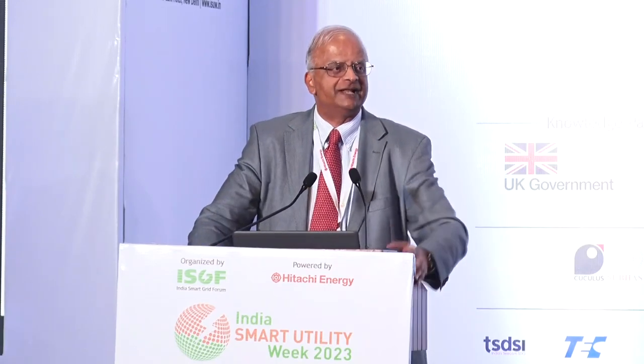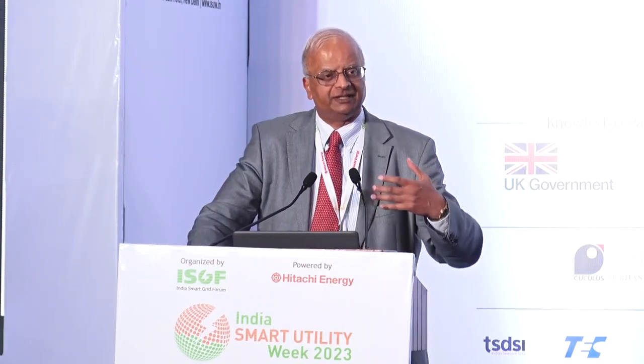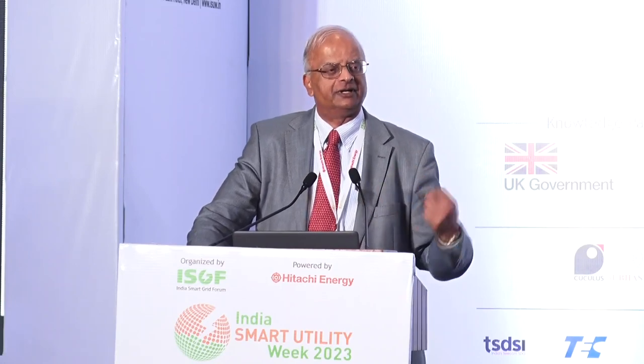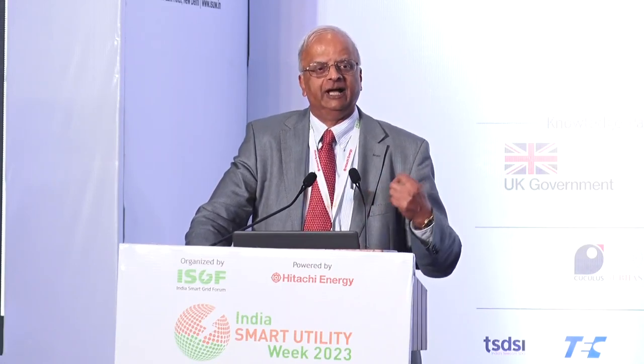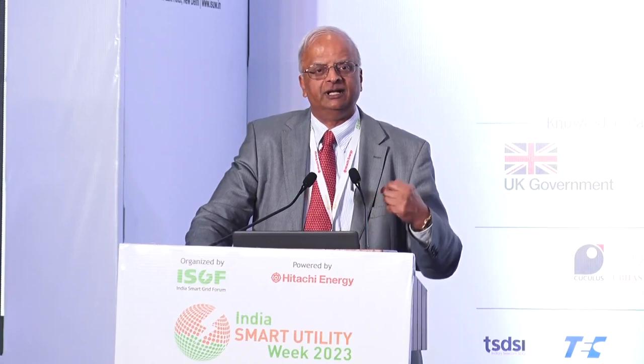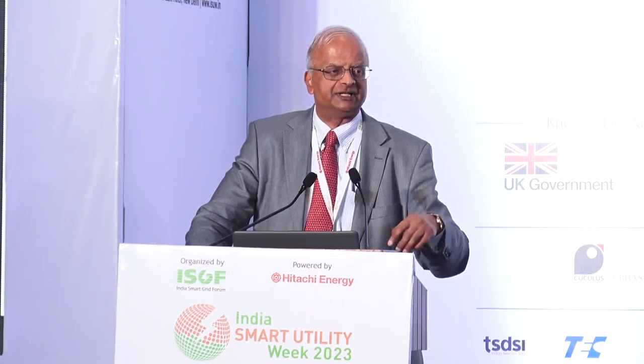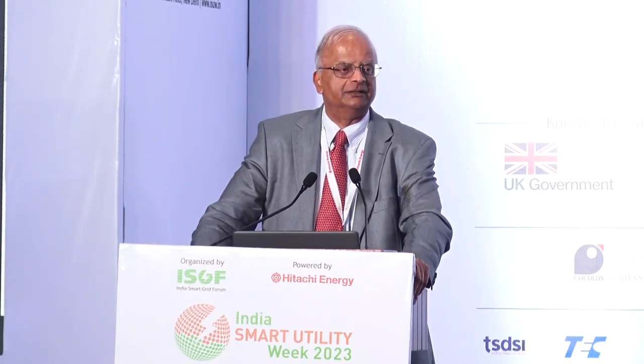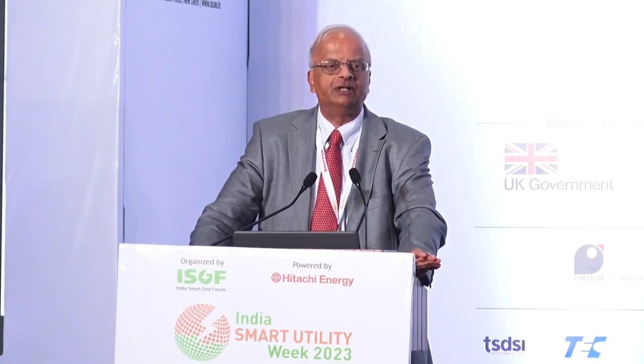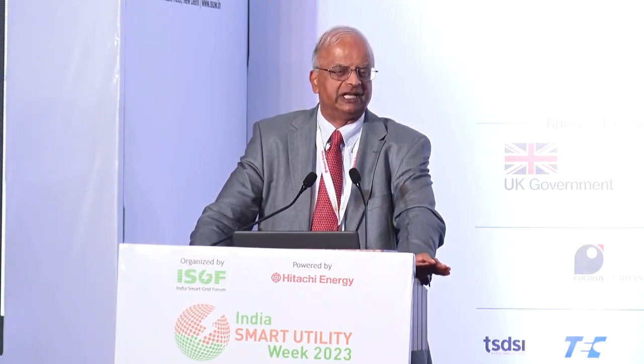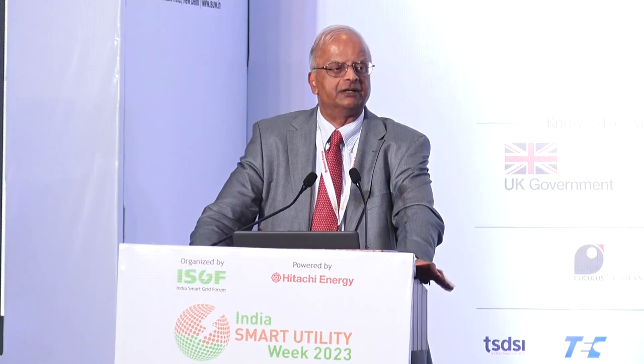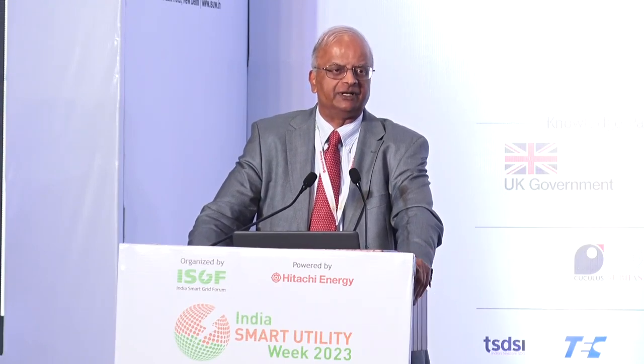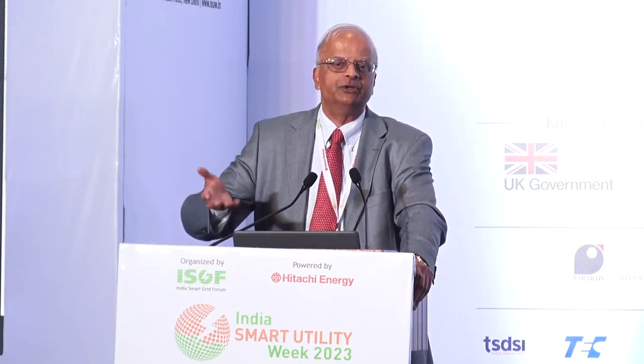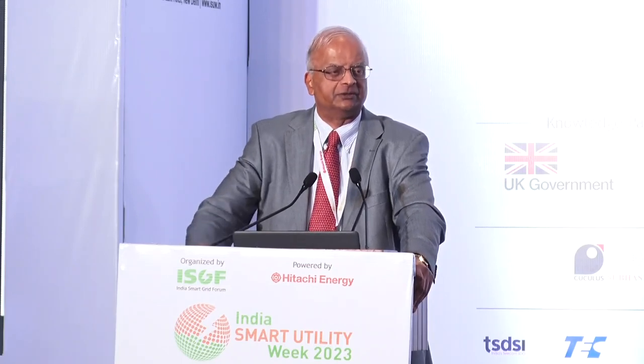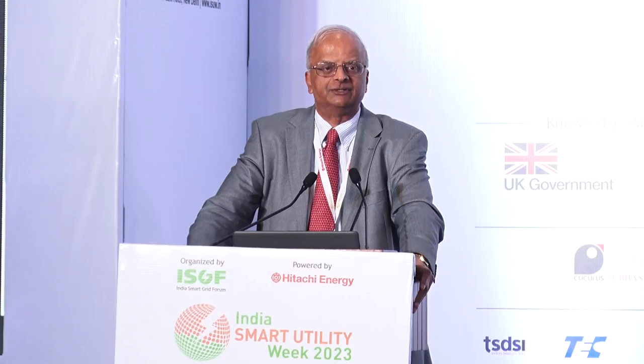So let's keep this as a dialogue. This is the second one of our dialogues, we had one last year, and perhaps we should continue this, because any time a standards organization puts a derating factor on paper, all the operators and asset owners essentially get their assets stranded. You have a transformer rated for 100 MVA, and they tell you it's only good for 90 MVA. Can you imagine? What do you do? You've just lost 10% of the ROA on that asset, and there's no way to recover that.